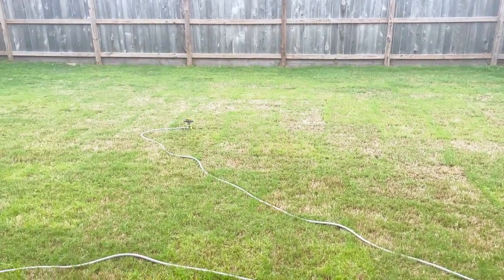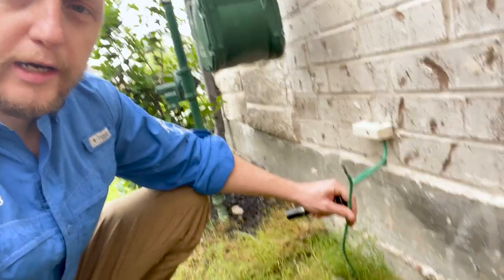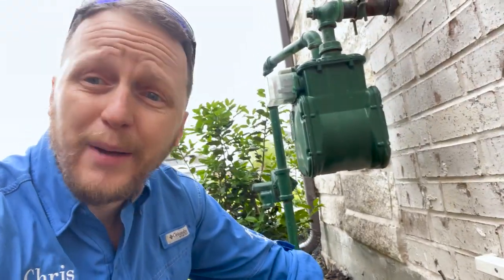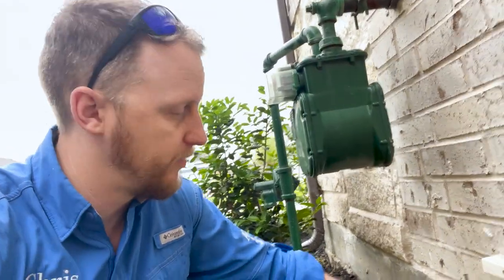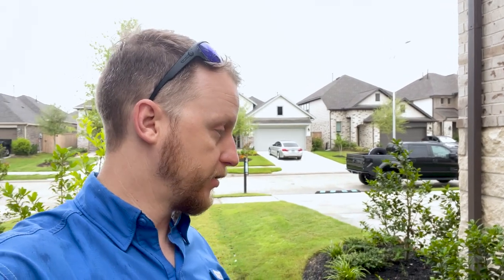This isn't inspection-related, but would this bother you? This is a $500,000 home and they don't include garage door openers or the backyard sprinkler system — only the front yard. One of the last finds: the ground electrode rod is pulled loose. This could have happened with a lawn company or it just wasn't tight enough in the bracket when installed. It's a pretty important find, and I'm surprised the other inspector didn't catch it.